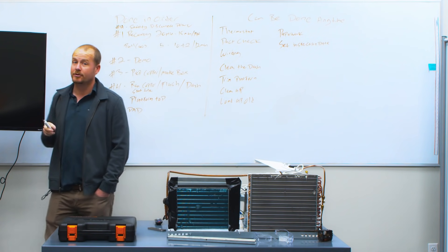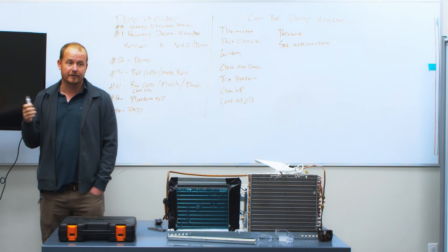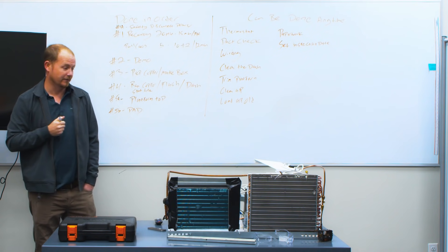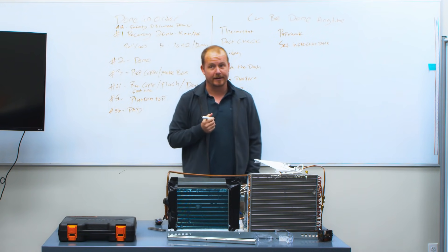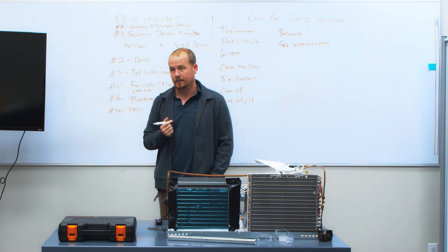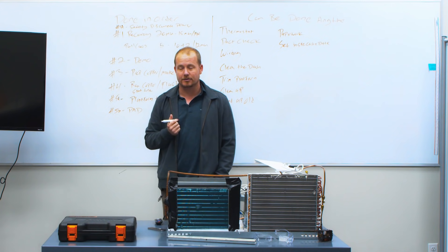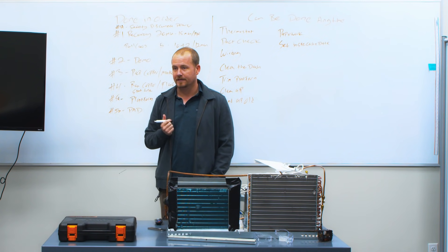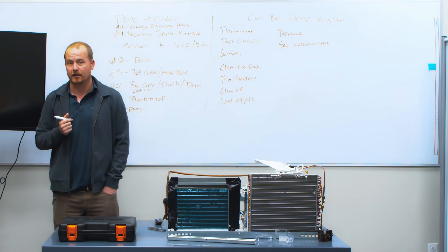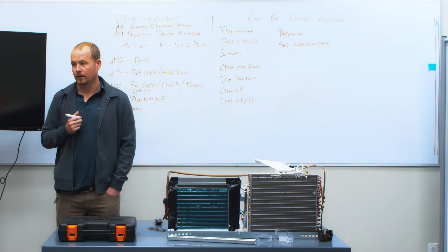The easiest way to charge is when it's under vacuum — go ahead and weigh in that amount into the liquid line before you even open the refrigerant lines. Why do you weigh into the liquid line and not the suction line? Because you're putting in liquid form, and if you put it in the suction line it'll sit right at the suction of the compressor, get pulled in, and potentially flood it — which you definitely don't want.